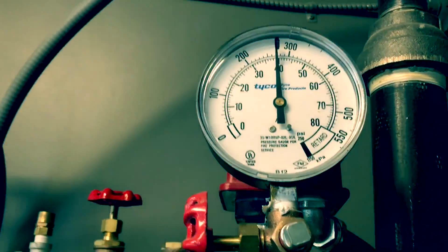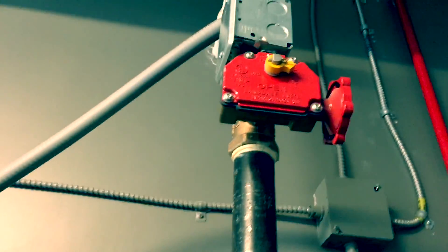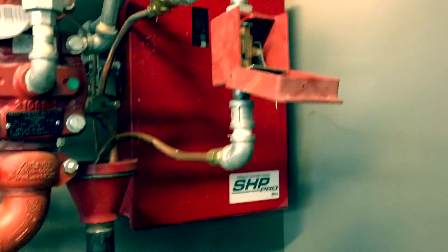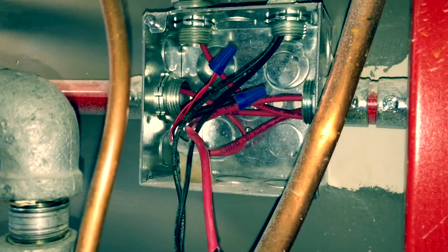Zeroes, got pressure on there, got the isolation valve closed. We're still getting air to the system anyway. Everything shut down, so that's why nothing went crazy. Now we got the system down, we are going to disconnect the electrical 24V to the solenoid actuator.